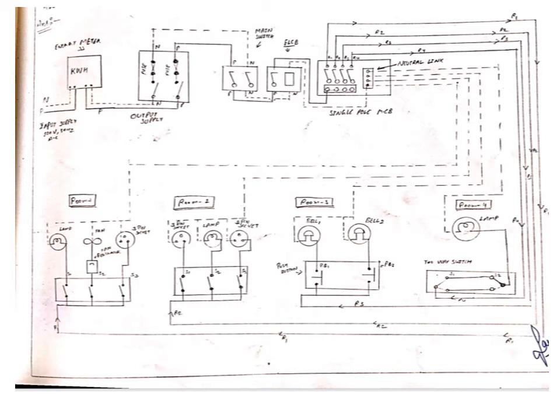Then for the second sub circuit, there is one 3-pin socket and one lamp, sorry, two 3-pin sockets and one lamp. So three switches we have connected in sub circuit 2. We have taken phase from the second single pole MCB and given to these three switches. And then the connection from switch 1 goes to the right point of the 3-pin socket, and the second switch connection goes to the lamp, and then the third one to the socket.